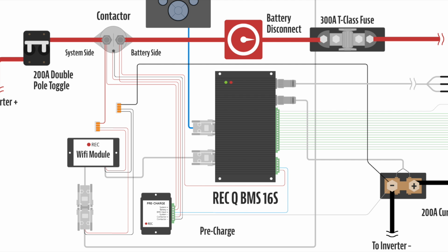The rest of the pre-charge connections are pretty self-explanatory. System Plus goes to the system side of your contactor, Battery Plus goes to the battery side of your contactor, System Negative goes to the negative side of your shunt, Contactor Positive goes to the positive contactor wire, and Contactor Negative goes to the negative contactor wire.